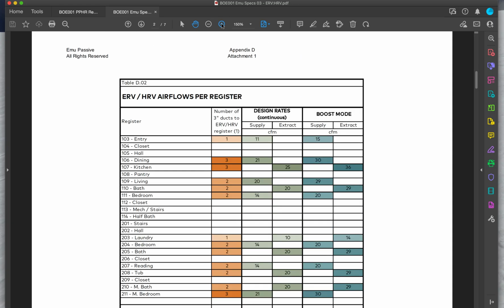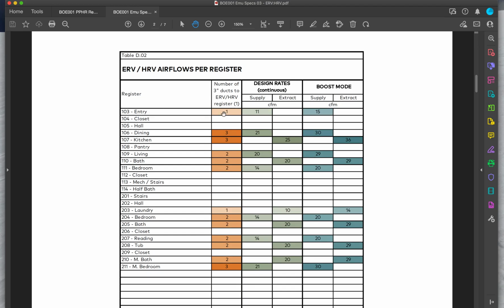Then here we have a list of all the individual rooms inside the building envelope, and we look at the design rates that dictate how much we supply to a room as opposed to how much we extract from a room. And the two totals, total supply and total extract, need to be balanced, meaning the total supply equals the total extract. We do not want to over supply or to under pressurize the building.